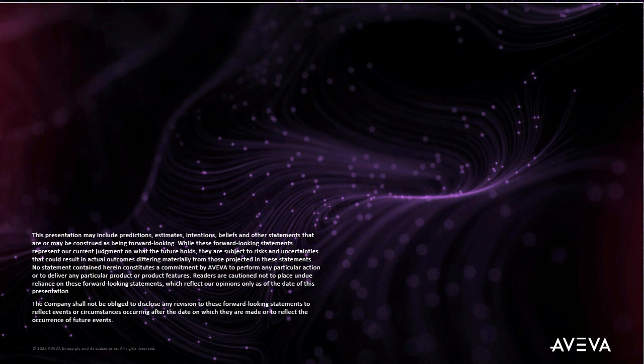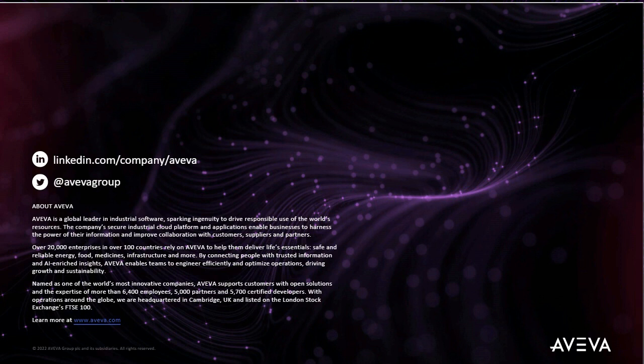Ernst, can older versions of System Platform be migrated seamlessly into 2023? Yes. Now, seamless is always a fun part. I would never recommend you take your new media or your new ISO and stick it into a running plant and go upgrade. The product is extremely configurable, and we try to cater for and test multiple galaxies during an upgrade, but we cannot cater for all of the iterations, combinations or permutations that we can have in our product. So I would always say, get yourself an offline galaxy and do the upgrade there.